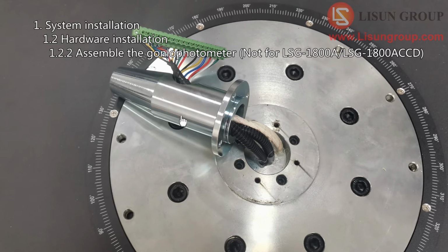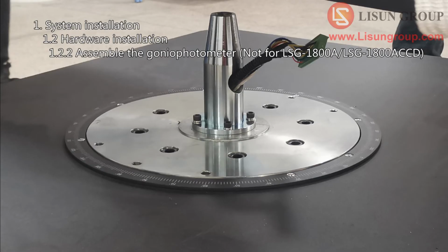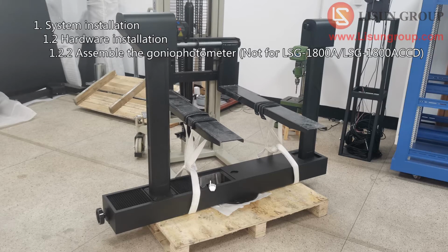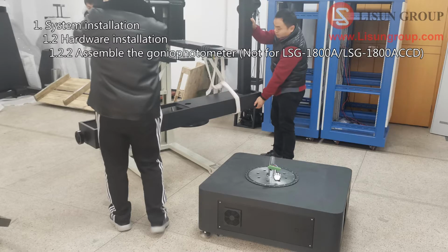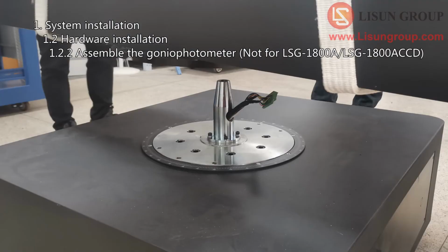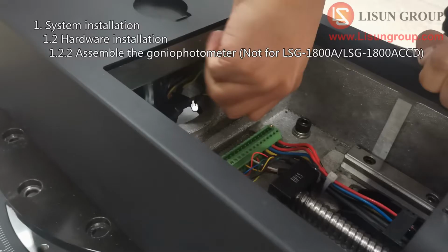There is a taper sleeve on the top of the base of the Goniophotometer. The sleeve and the base are engraved with one same number. Make sure the numbers are in the same direction and fix the sleeve to the base using the screws. Open the dust cover of the turntable. There is the terminal bar under the dust cover. Lift the turntable using a forklift. There is also a terminal bar out of the taper sleeve. Make sure they are in the same direction. Put the turntable down on the base slowly. Protect the terminal bar of the sleeve and make sure it goes through the hole successfully.